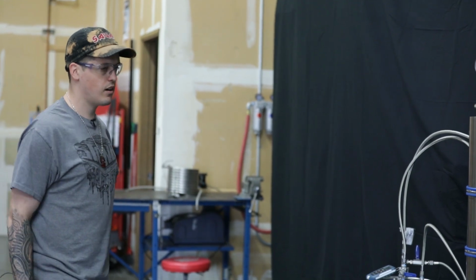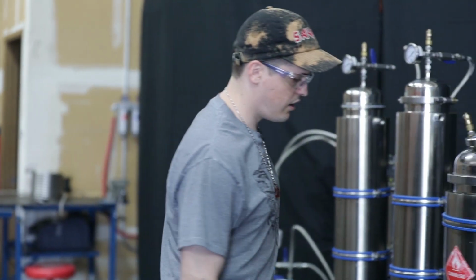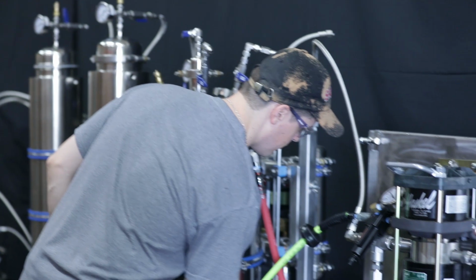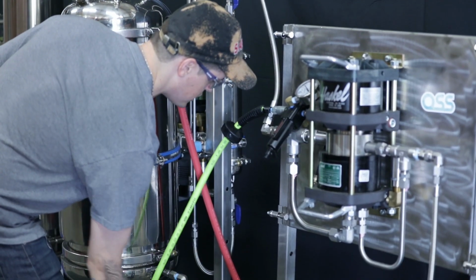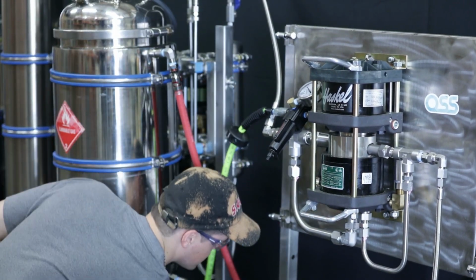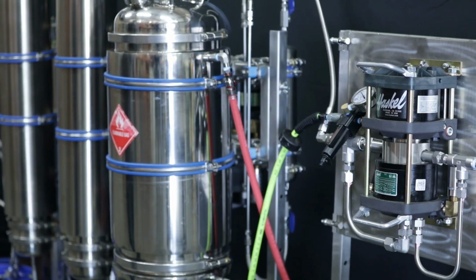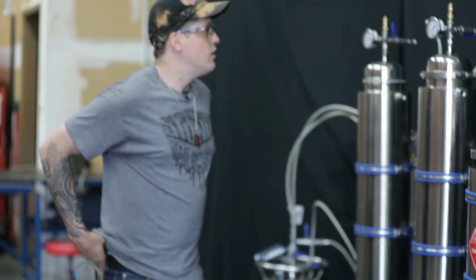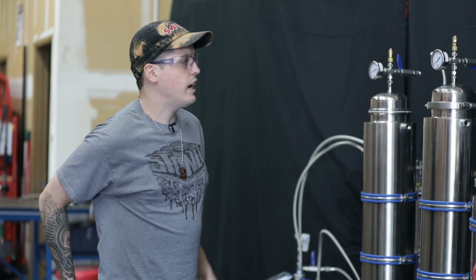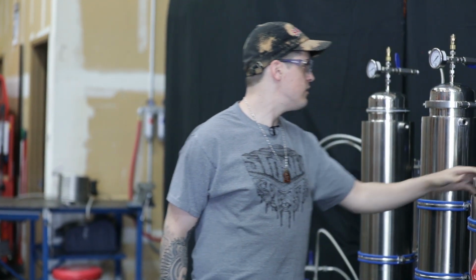Now we've got our recovery pump hooked up in line here. We've got our vacuum pump pulling down a full vacuum, which looks like it's reached. Just going to tuck this hose back a little bit. The gauges are reading a full negative 30 inches of mercury.